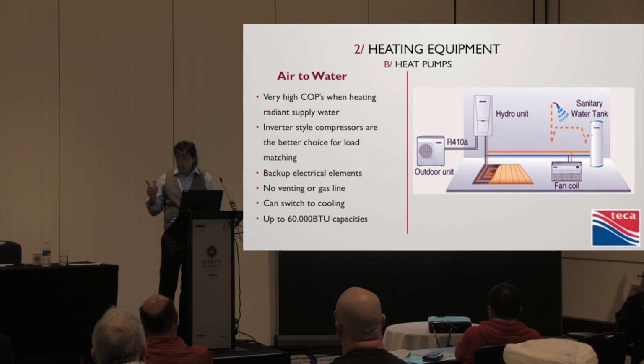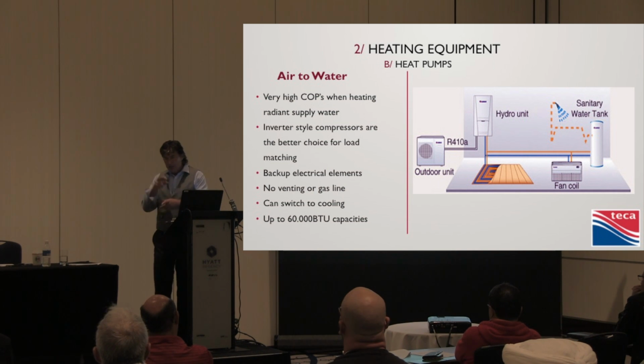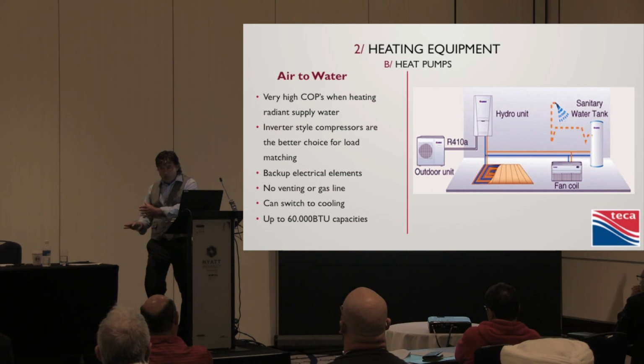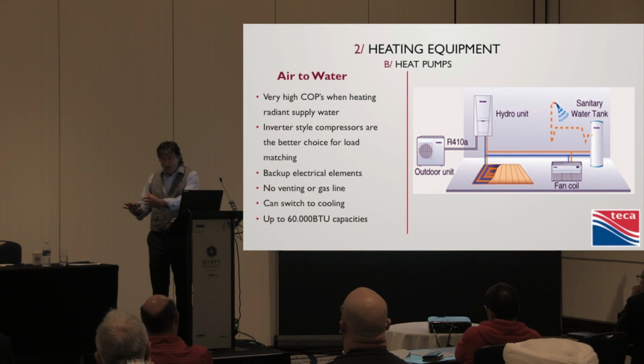any means, but I was standing beside, they had the outdoor unit inside in the training room and then the fan coil right there, and they said, well, go ahead, what do you think of it? I go, well, turn it on, let's find out. They said it is on. Get out of town, there's no way. So the condenser fan wasn't even running. However, the inverter compressor, it starts at 0 amps and it sort of modulates up, and it was so little that I had to get the amp meter out and actually clip it on there. That thing's actually working. So this is years ago.